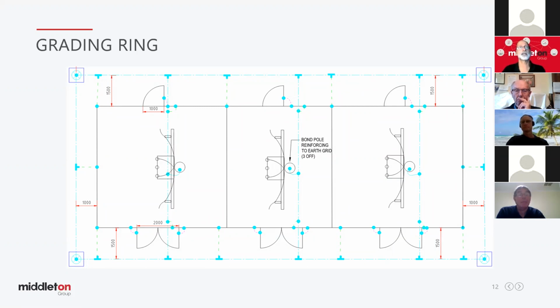So in this design, to reduce the voltage between the fence and the surface, the ground that potentially Joe Public's standing on, a metre from the fence, a grading ring's been installed, which is a ring of bare copper, 500 mil under the ground and a metre out from the fence, bonded to the earthing system. This will bring the surface outside of the fence up in volts. If there's an earth fault there, you'll have an EPR at the transformer, and all the copper that connects to the earth grid and to the ground will increase the surface voltage there, thereby reducing the voltage from the fence to the surface that the person's standing on.